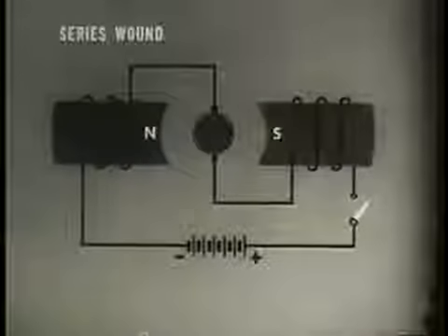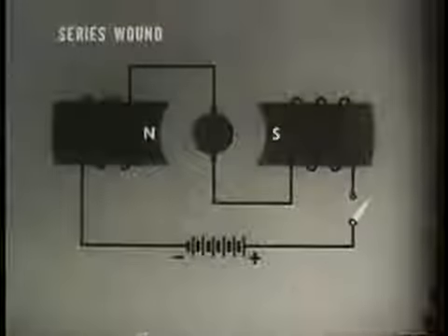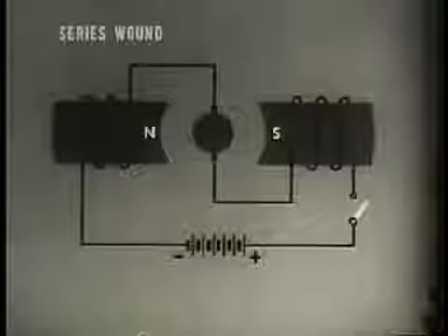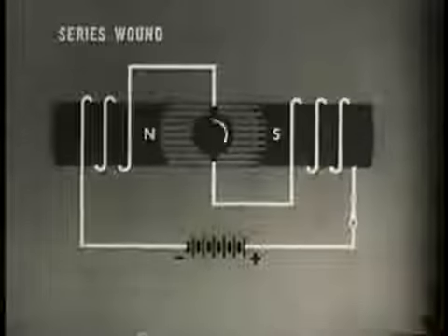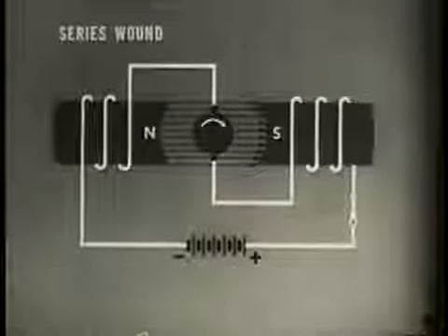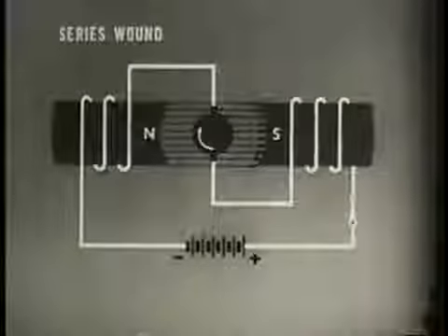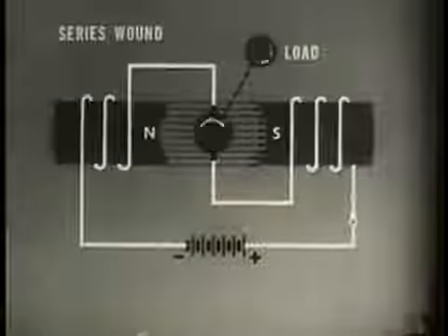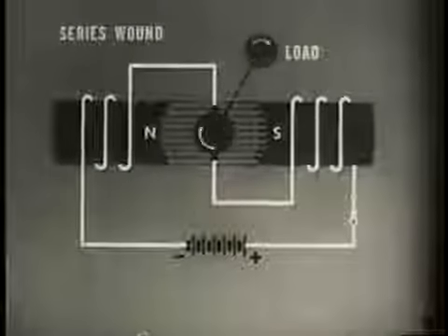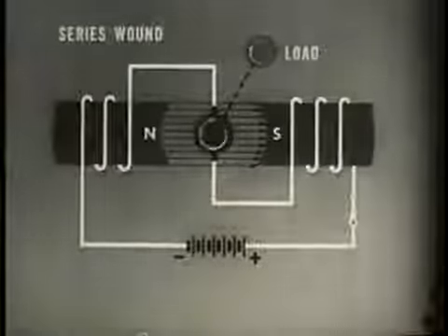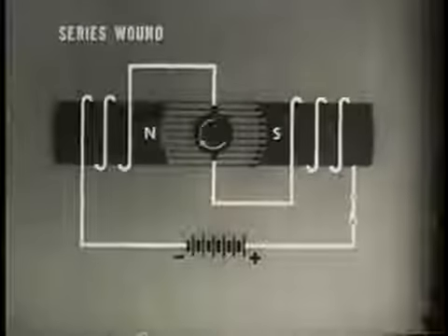The series wound motor has good starting torque or turning force. Torque depends on armature current and on field strength. Since field strength is proportional to current, the high starting current before CEMF is developed affects torque as the square of the current. The motor begins to turn, attempting to develop enough CEMF to completely oppose the applied EMF. The load prevents this, acting to control the speed of the motor. But if the load is suddenly removed, like in the case of a broken belt, the motor will build up speed trying to develop more CEMF until it destroys itself.